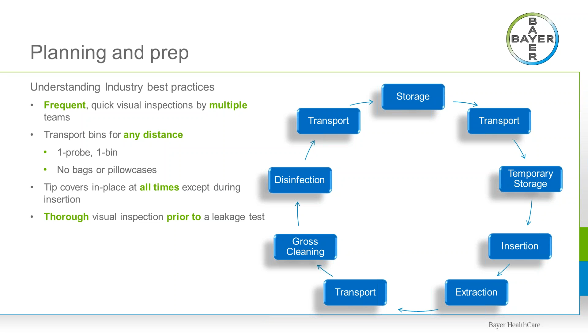It's really critical to perform a thorough visual inspection prior to performing a leakage test. So now we're down into central processing, where the probe is going to be high-level disinfected, if not gross cleaning. These folks have the critical role of performing a thorough visual inspection. A leakage test is really designed to find the holes that really can't be visualized with the naked eye. And it really needs to be performed right before disinfection.